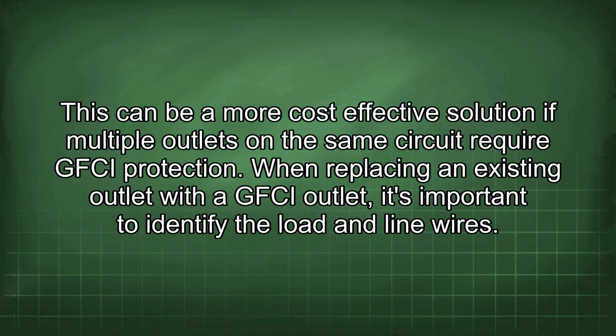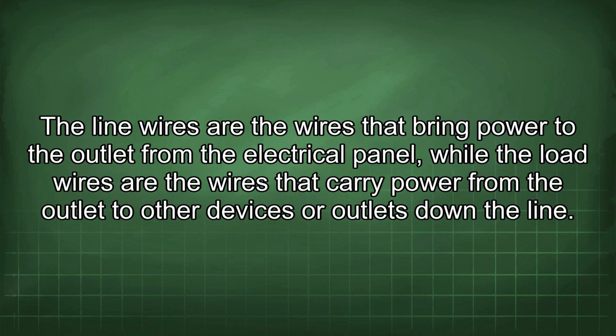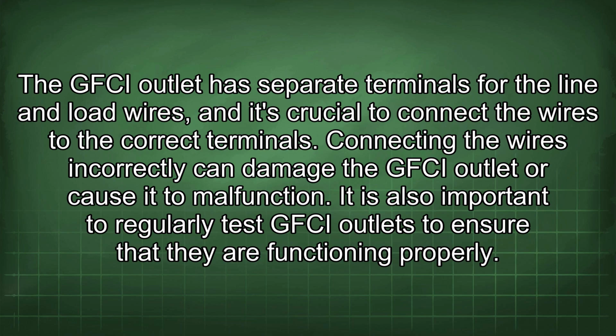When replacing an existing outlet with a GFCI outlet, it's important to identify the load and line wires. The line wires are the wires that bring power to the outlet from the electrical panel, while the load wires are the wires that carry power from the outlet to other devices or outlets down the line. The GFCI outlet has separate terminals for the line and load wires, and it's crucial to connect the wires to the correct terminals. Connecting the wires incorrectly can damage the GFCI outlet or cause it to malfunction.